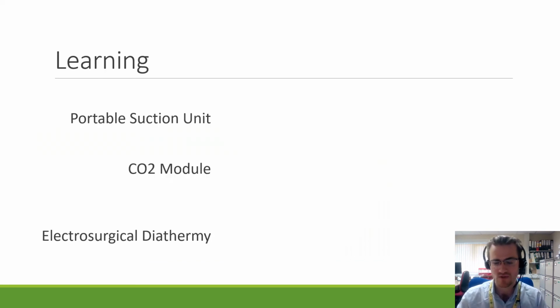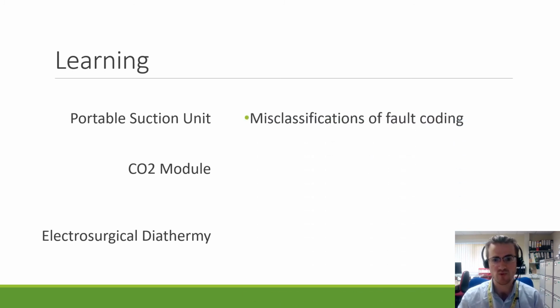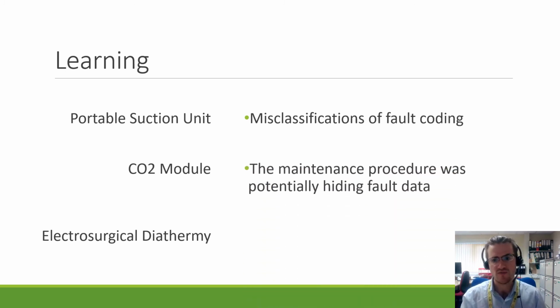And even more so, we managed to gain some learning from each device. So the portable suction, we saw that there was misclassification of fault coding. We thought we determined that this wasn't enough to significantly affect our quantitative analysis, but as a result, we implemented stricter teaching around the fault coding. CO2 modules, we found that the maintenance procedure was potentially hiding some fault data, so that was changed and relayed to staff, and we have a more robust process for that now.